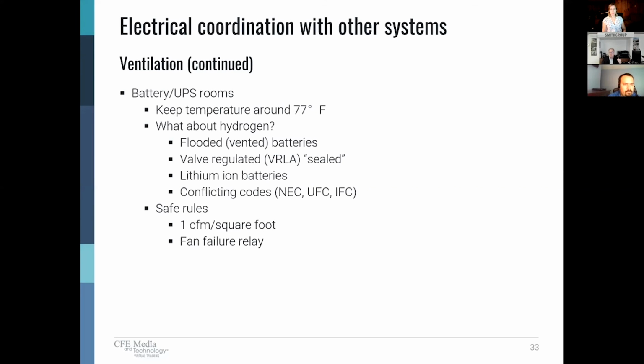They last longer, but there are new codes and conflicting codes coming up on the safety of lithium ion batteries and the potential for explosion. So work with your fire protection engineer, your code engineer. The general safe rule is 1 CFM per square foot. And if there's a ventilation fan in there, make sure there's a fan failure relay so you know if the ventilation in the battery room has failed. Next.